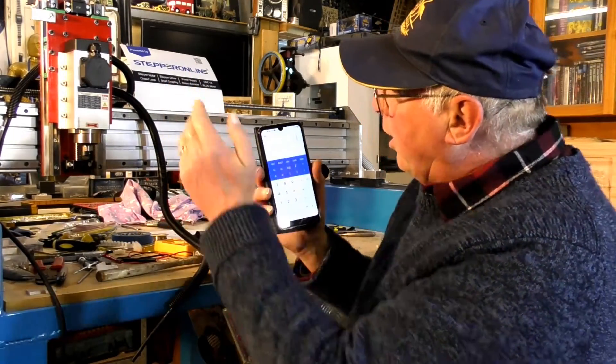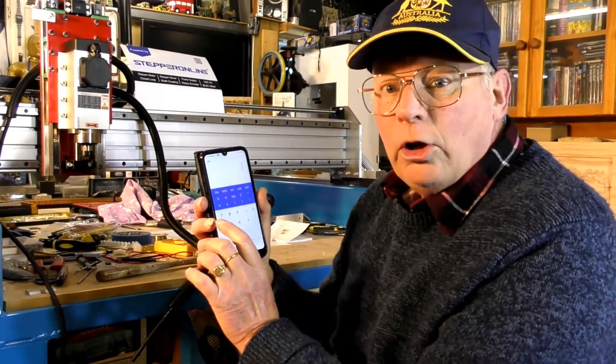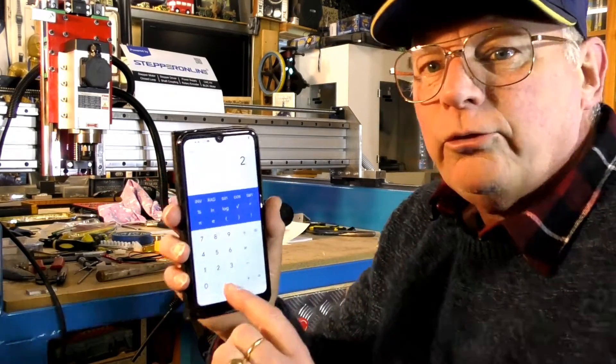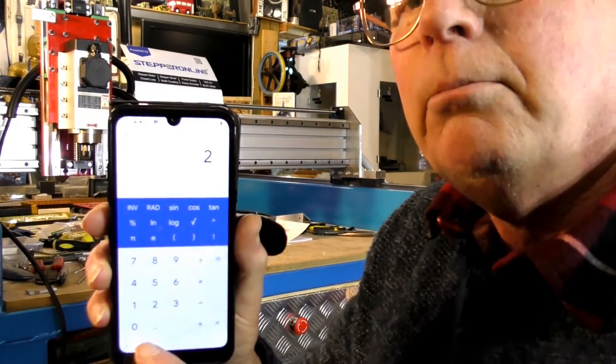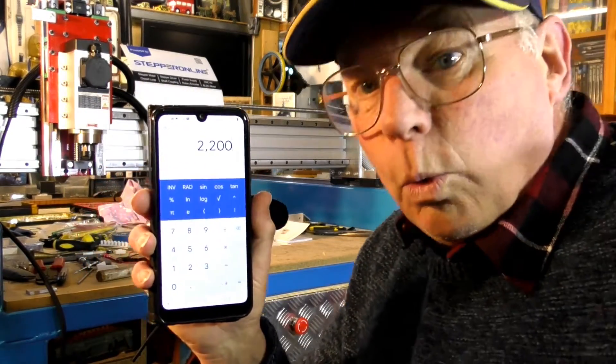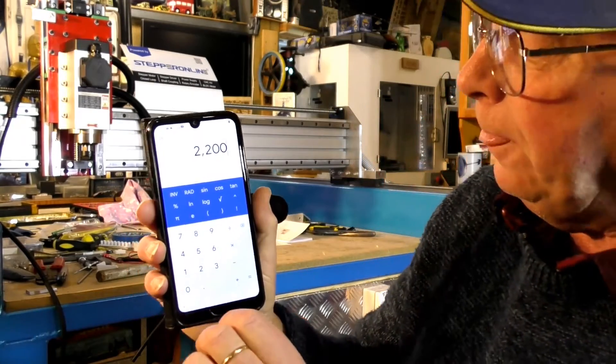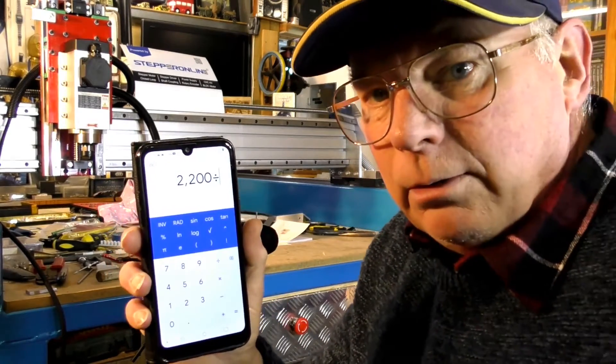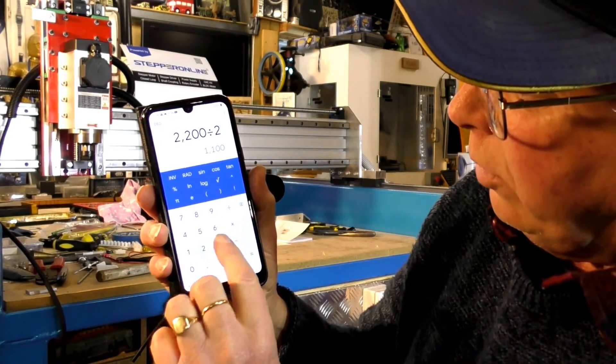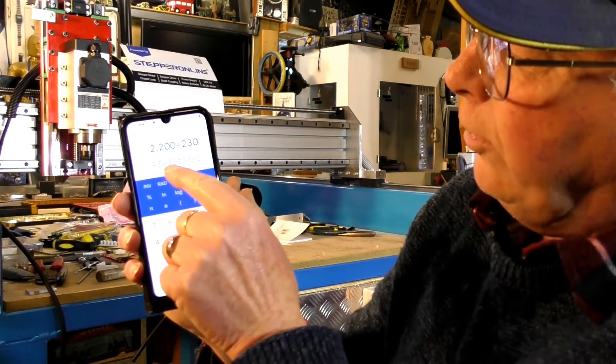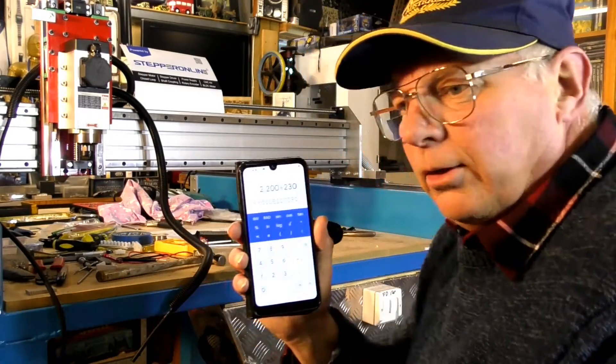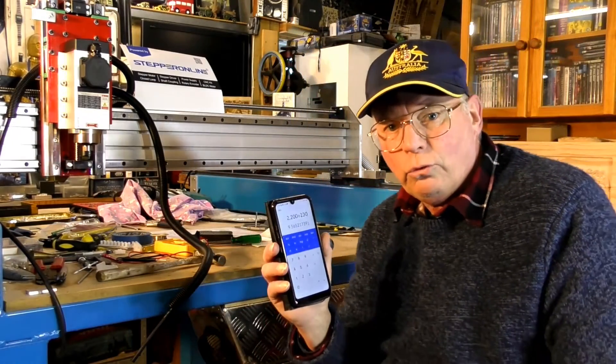In our case this is 2.2 kilowatt, so that's 2,200 watts. 2,200 watts divided by the circuit voltage which is 230. There's your answer, 9.56 amps. That's the maximum draw.